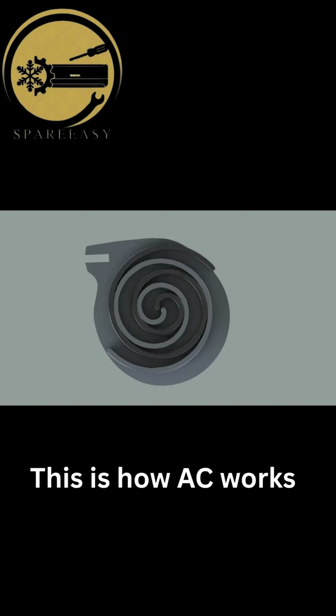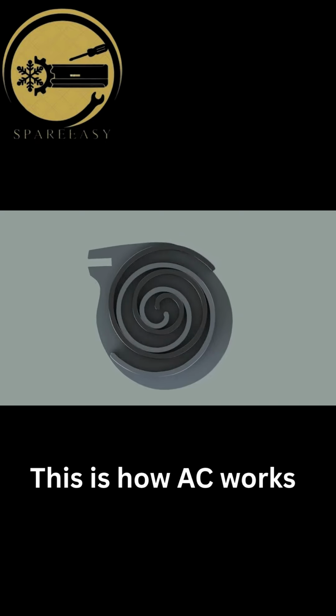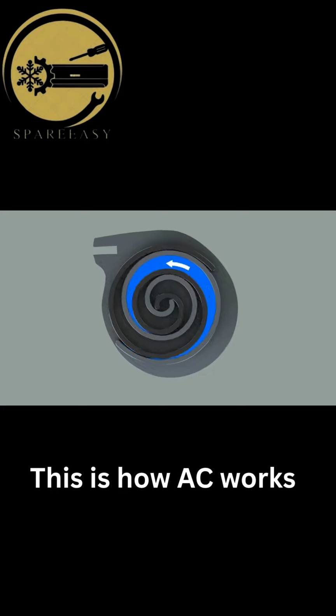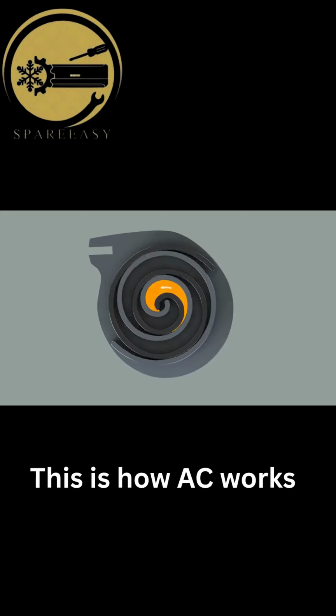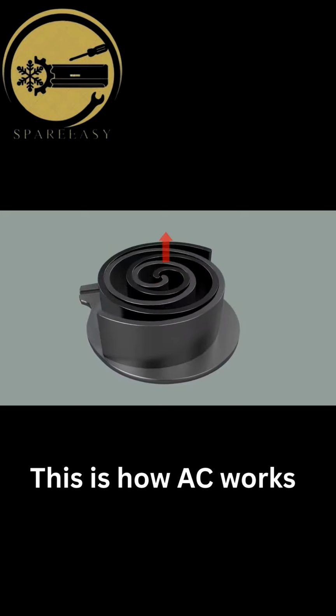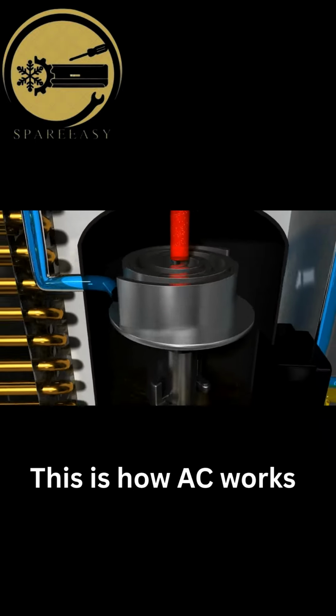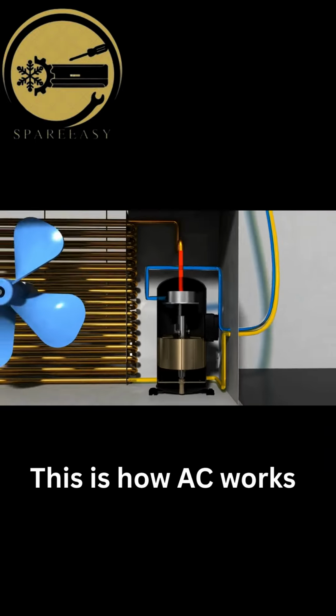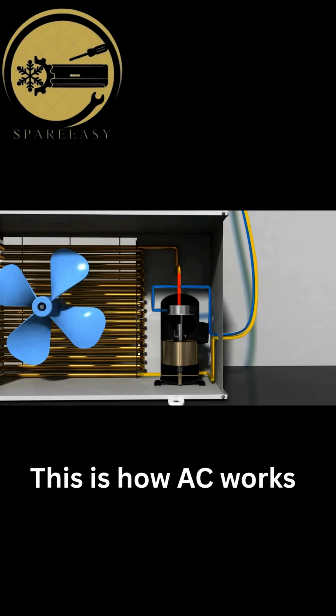The scroll compressor. There are two scrolls, of which one is fixed, and the other rolls constantly. As more air coming through the entrance gets inside the scroll, space becomes crowded. As there is less space now, gas becomes more compressed, and is discharged from the middle of the scroll in a compressed state. The reason for using such a type of compressor is the efficiency of space utilization. This type of compressor allows the machinery to become smaller in size and reduces noise as well as vibration.